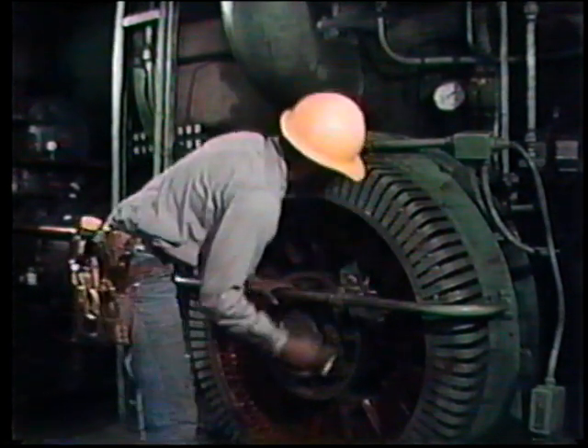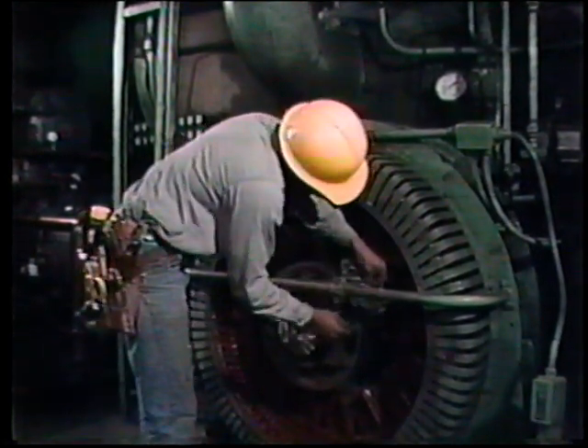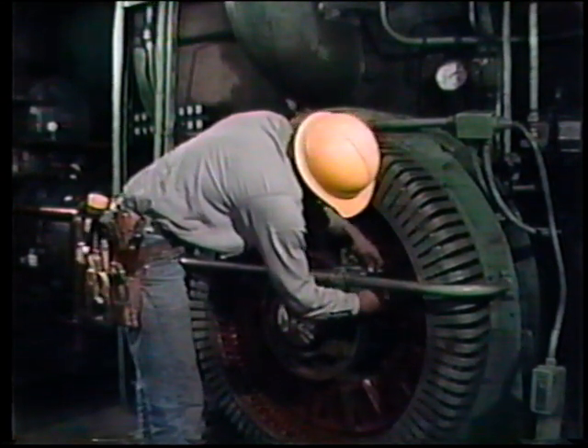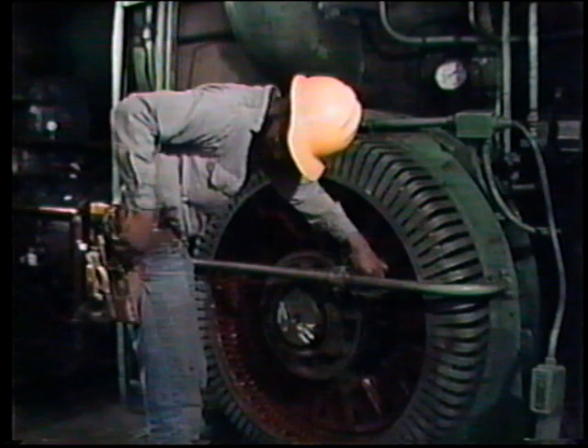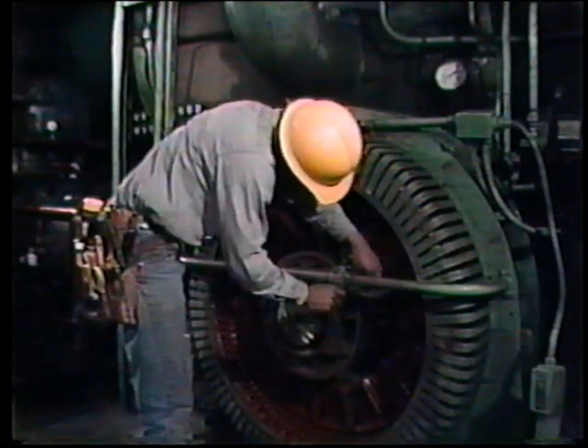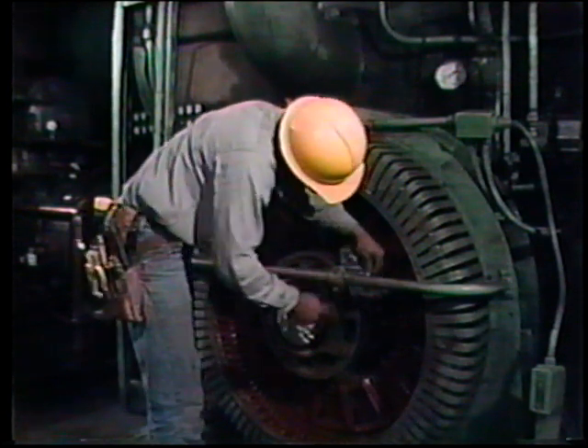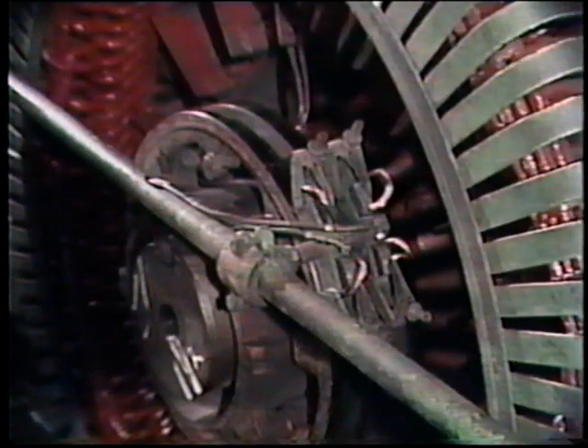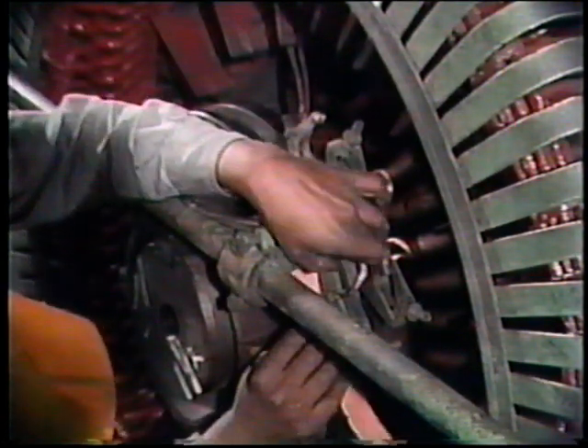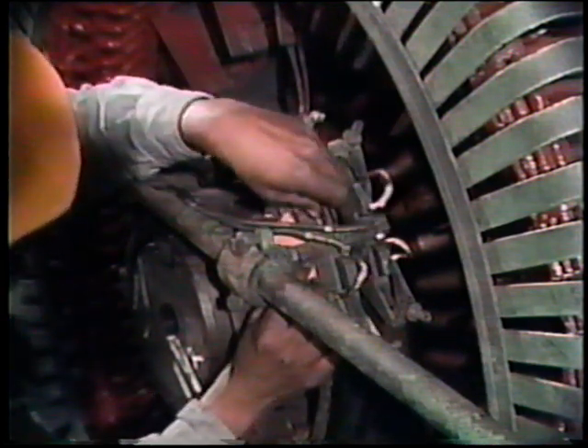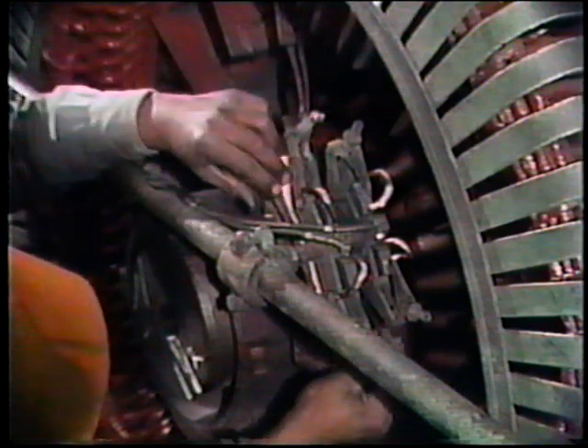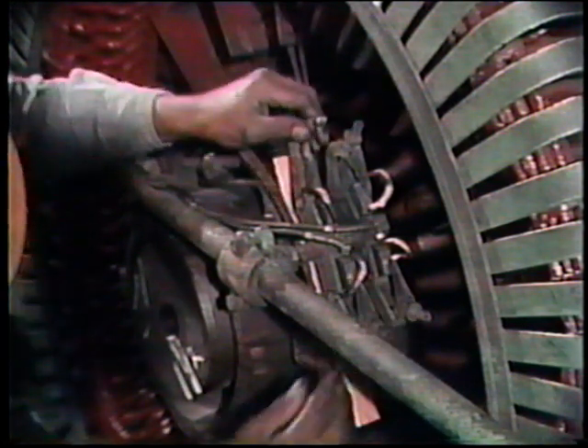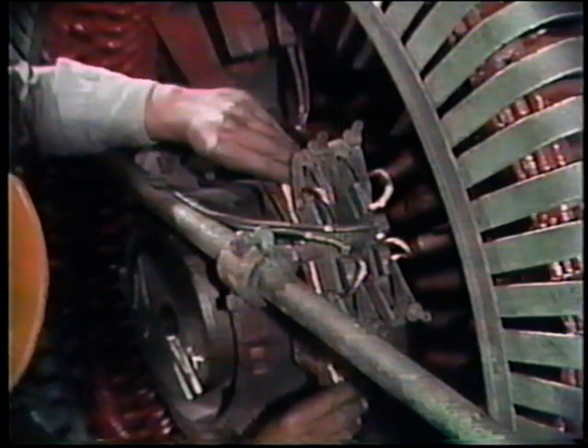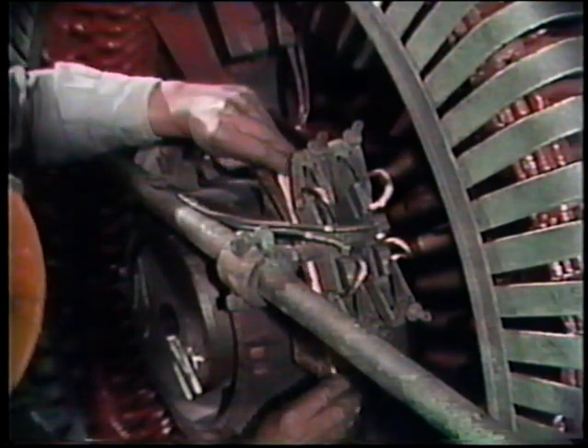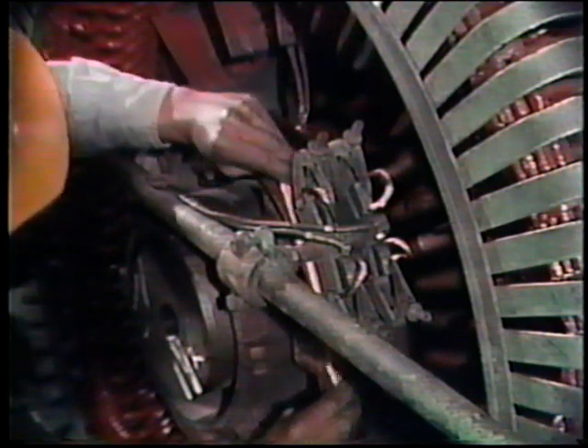As a rule of thumb, if any of the brushes are worn below 1/4 of their useful length, the brushes must be replaced. In some plants, when any of the brushes require replacing because of excessive wear, all of the brushes are replaced. Follow the procedures used in your plant. For proper brush performance, all brushes should be seated to the curvature of their slip rings when they are replaced. Improper seating can cause sparking and overheating that can damage both slip rings and brushes. To seat the brushes, a piece of sandpaper is placed between the slip rings and brushes. The sandpaper is then moved back and forth along the underside of the brushes.